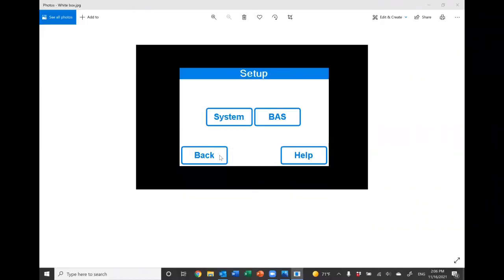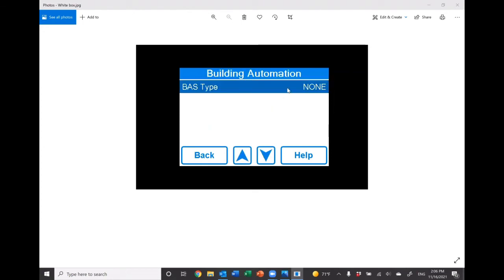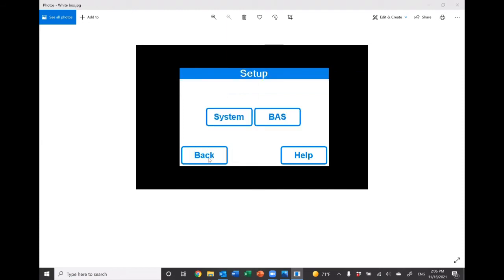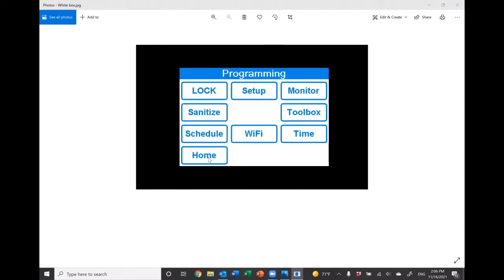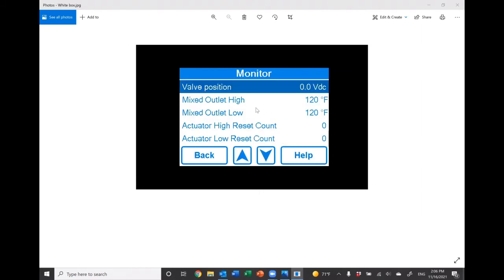After that, we back up. This also has your BAS, which is an integrated feature that comes standard in the controller, BAS compatible and ready to go. After that, you set your time, your toolbox, your monitor, so that you can see what was the highest temperature this valve has reached since we've been in here and set it last, what's the lowest temperature, and so on down the line for these different data points.